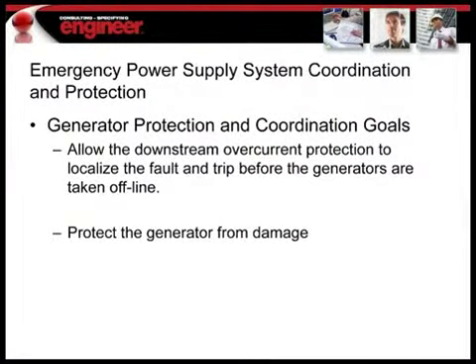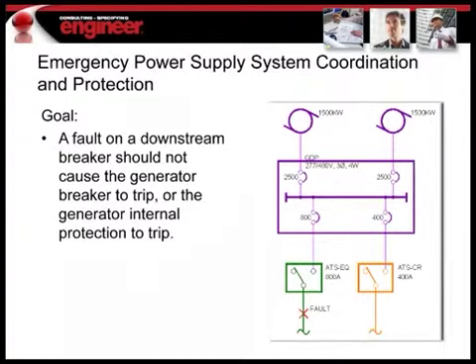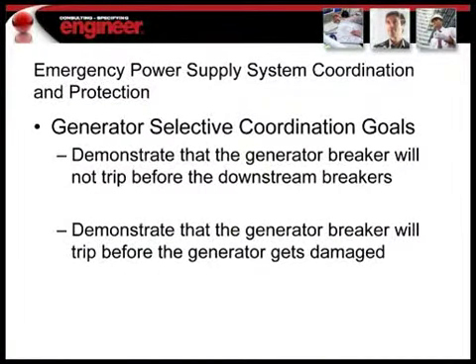Okay, so let's get into coordination. The goal of coordination is to allow the downstream breakers, the breaker that feeds the ATS EQ, to trip before the generator is taken offline. But at the same time, we want to make sure that our generator breakers, which are there to protect the generator, do that. It's pretty straightforward goals, but that's it. So here's that example again that we talked about earlier, where we have the fault downstream going through an 800 to the 2500. We want to make sure that the 800 trips before the 2500, and that the 2500 will protect the generator. Okay, so there are the goals.